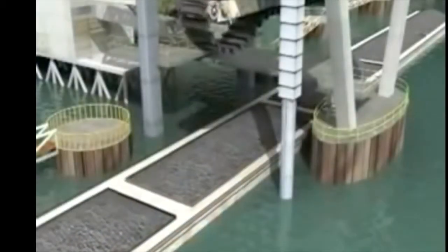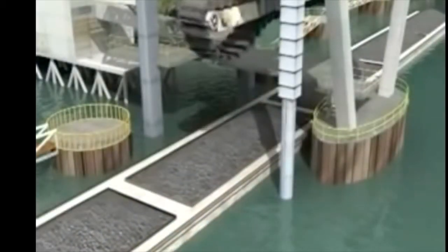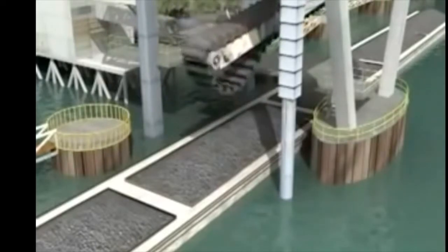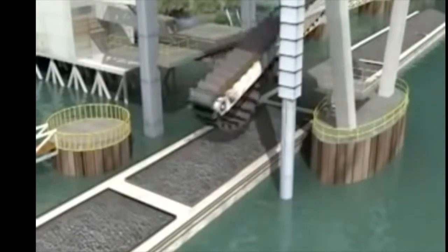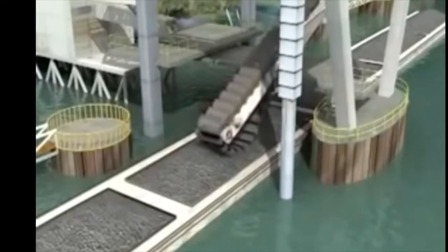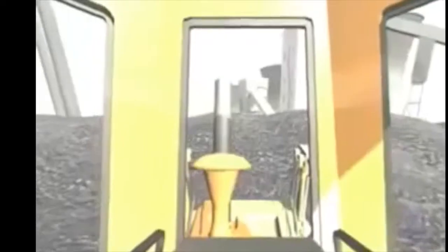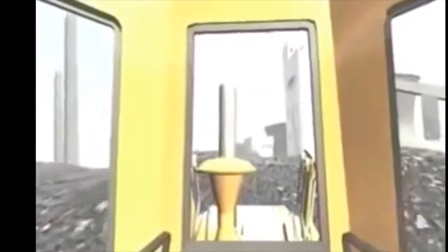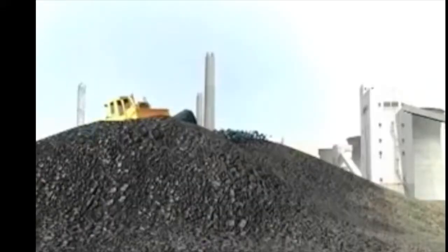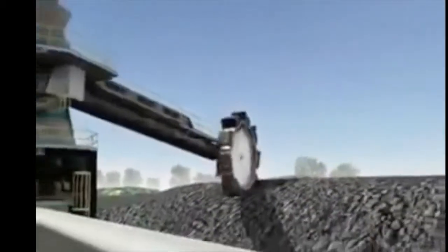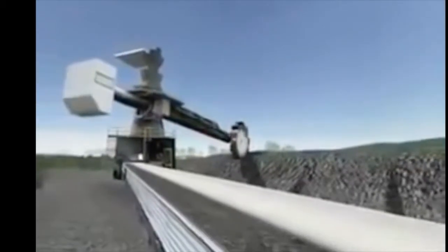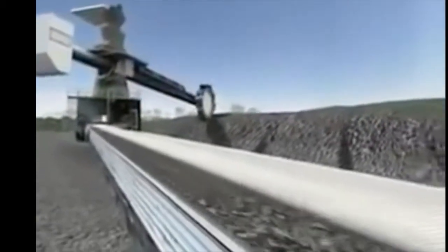Generating electricity requires a fuel source. At this plant, the fuel source is coal, which arrives mainly by barge. Each barge delivers 1,500 tons of coal, enough to keep the plant running for a couple of hours. The plant uses about 21,000 tons of coal each day, and a device called a stacker reclaimer scoops the coal into a conveyor, which transports the coal into the plant, as you can see here.